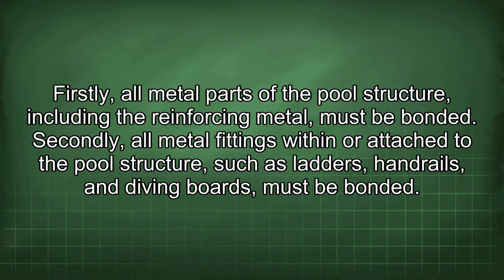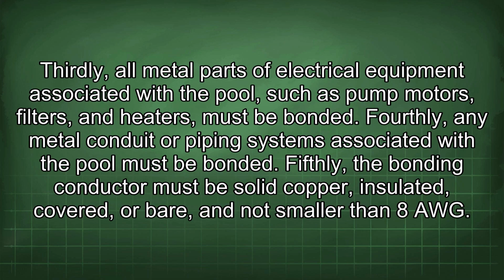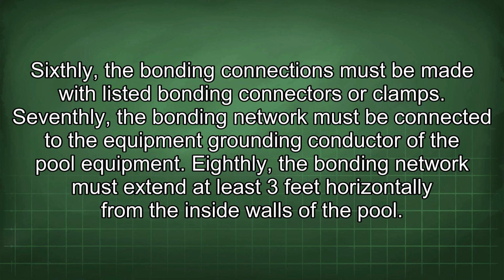Firstly, all metal parts of the pool structure, including the reinforcing metal, must be bonded. Secondly, all metal fittings within or attached to the pool structure, such as ladders, handrails, and diving boards, must be bonded. Thirdly, all metal parts of electrical equipment associated with the pool, such as pump motors, filters, and heaters, must be bonded. Fourthly, any metal conduit or piping systems associated with the pool must be bonded. Fifthly, the bonding conductor must be solid copper, insulated, covered, or bare, and not smaller than 8 AWG. Sixthly, the bonding connections must be made with listed bonding connectors or clamps.